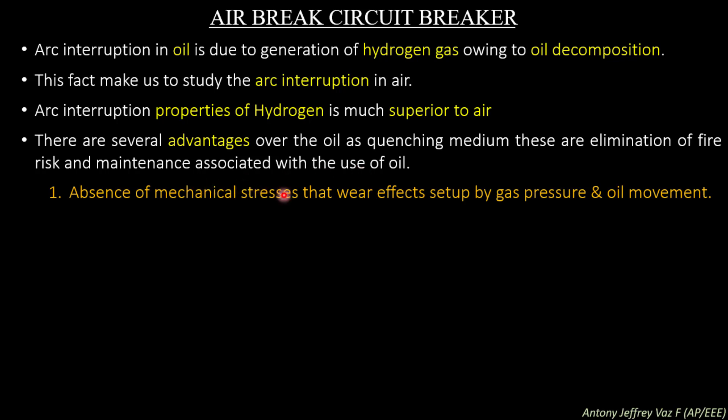Another advantage is the absence of mechanical stresses, wear effects set up by gas pressure and oil movement. If air is used, the wear and tear caused by the movement of air is not present. If an oil circuit breaker is used, the parts present in the oil and the gas created by decomposition of oil will corrode the metal parts of the circuit breaker. So the air circuit breaker is superior to an oil circuit breaker in terms of maintenance.